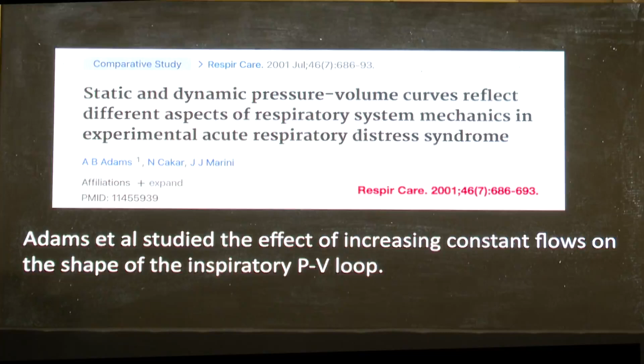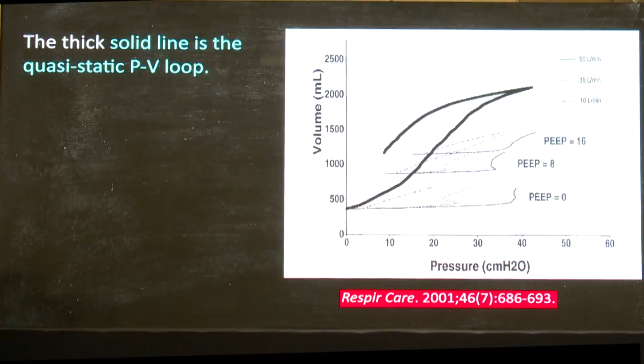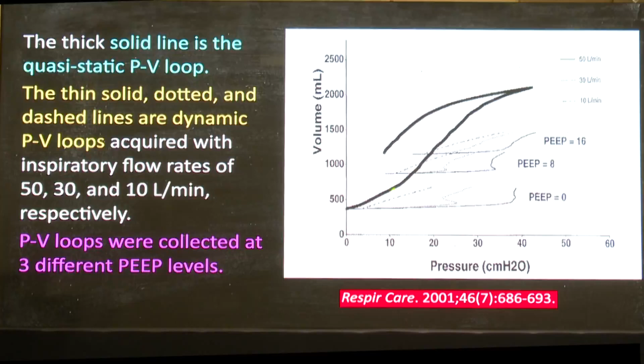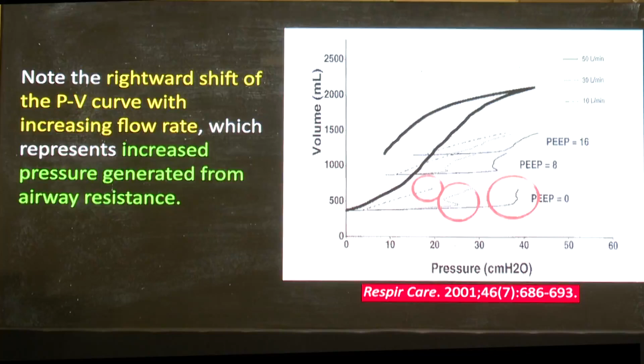So this dark loop is the static PV loop, and these are three loops which are dynamic PV loops. Dynamic PV loops, as I said, are the loops which we normally get on our ventilator, and these three loops are at three flows of 10, 30 and 50 liters per minute, and at three positive end-expiratory pressures of 0, 8 and 16. And we can see here that as the flow is increasing, you can see the loops are moving towards the right. So just by increasing the flow, we are generating a kind of inflection point, a pseudo inflection point, just by increasing the gas flow. And also when the PEEP is increasing, we are seeing that the volume is increasing.